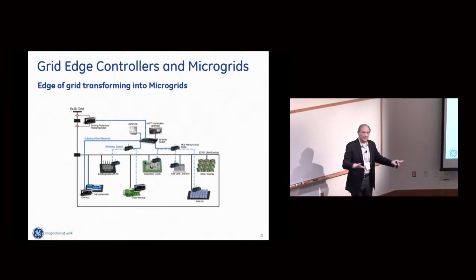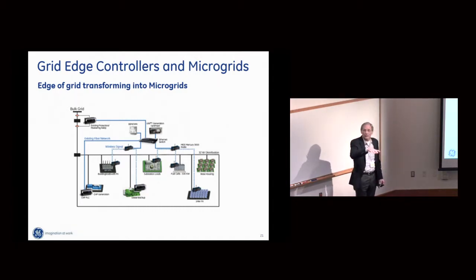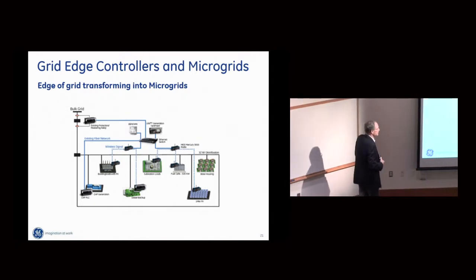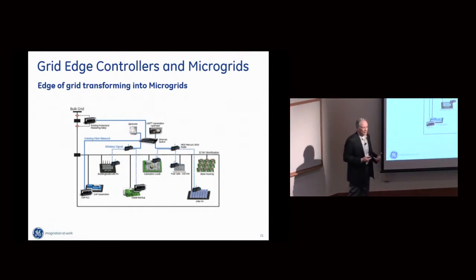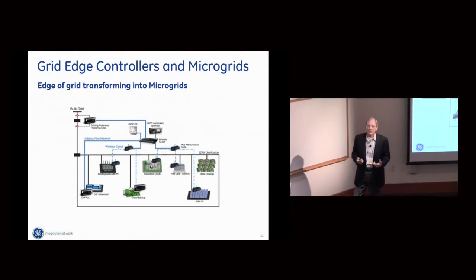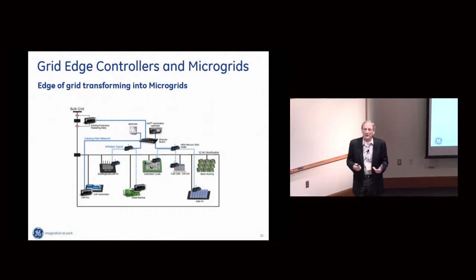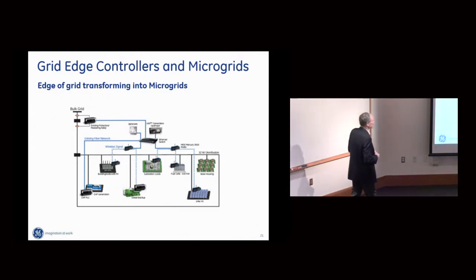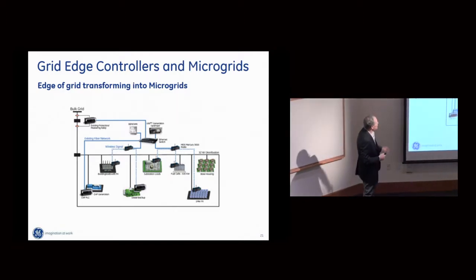They're installed in many utilities in the US and Mexico, one level up in the hierarchy from a control point of view. At the lowest level you have the inverters that couple the renewables to the grid. Next level up you have these grid edge controllers. They're small, on the low voltage network, and not very expensive. You place a number of them on the low voltage network, and load flow studies and simulation studies determine how many you need and where they should be placed. These are power electronic based.